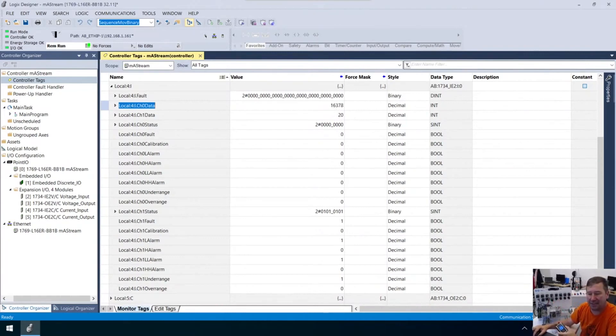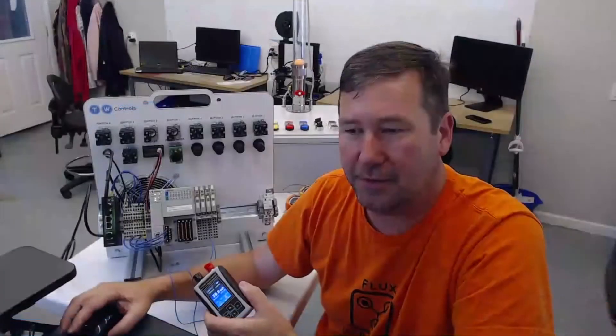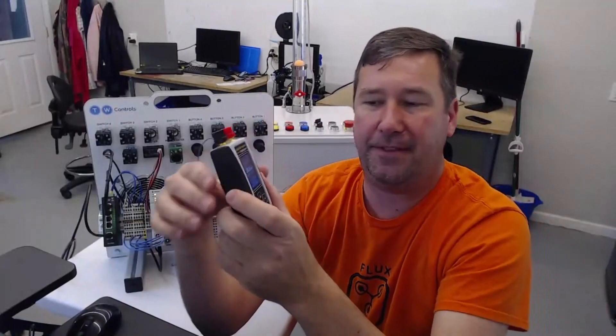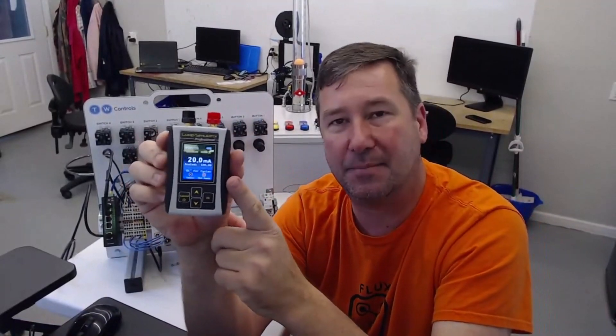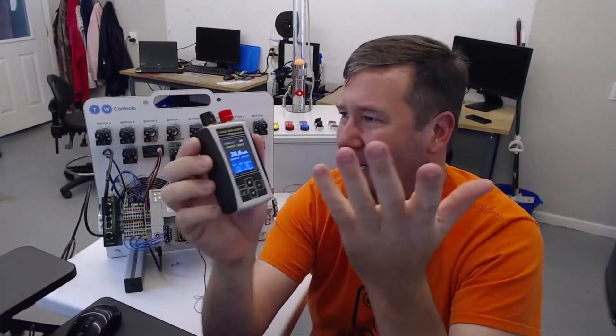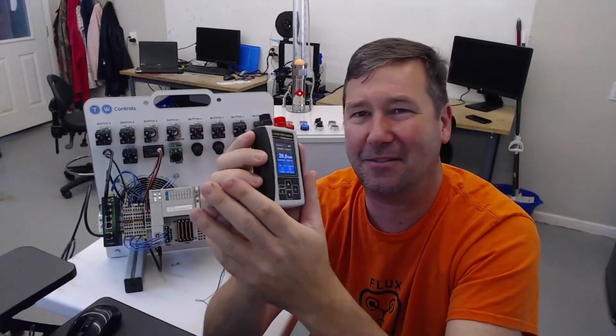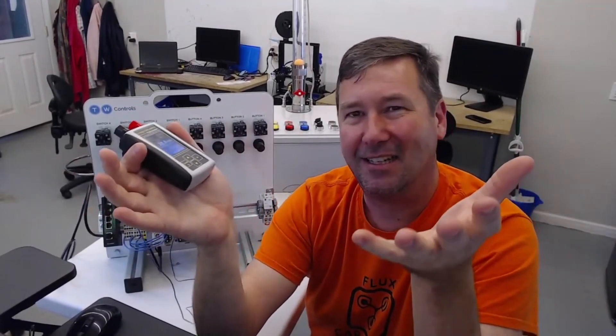These are the rough values of this. We're at 20 milliamps now and we're seeing 16,378. I see this all the time. People will put those values in, they'll use the raw values and figure out they need to kick a pump on at like 12,000 raw value. Well no, we don't need to do that. We need to figure out some scaling. We need to do some math.